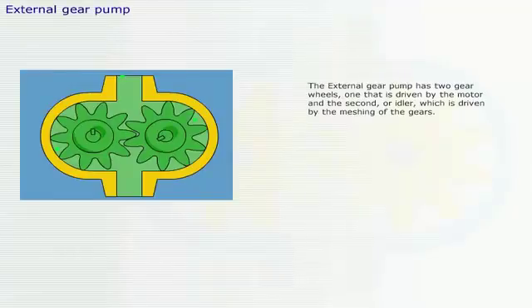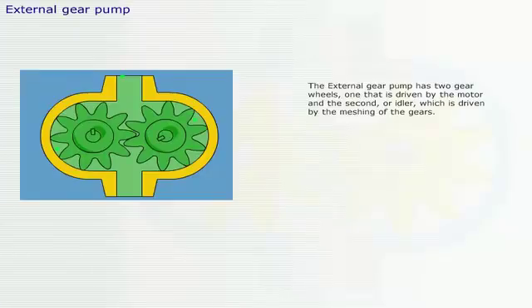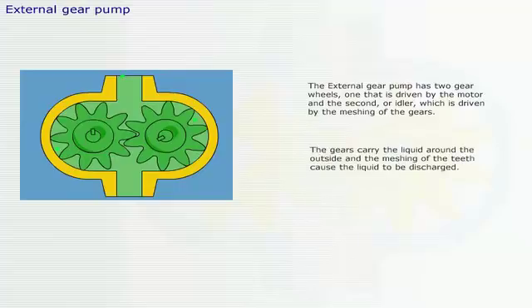The external gear pump has two gear wheels, one driven by the motor, and the second, or idler, which is driven by the meshing of the gears. The gears carry the liquid around the outside, and the meshing of the teeth cause the liquid to be discharged.